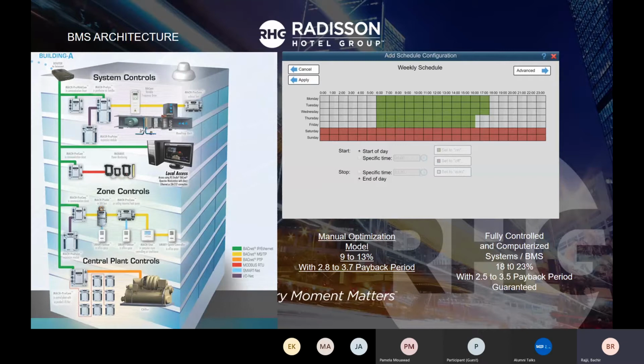But there is always human error, which means an automated system is more accurate with much less error. From studies and experience, a manual optimization model following a checklist would save between 9 to 13%, guaranteed, with a payback of 2.8 to 3.7 years depending on the hotel, equipment capacity, etc. However, a fully controlled BMS system would guarantee savings between 18 to 23%, with a payback period of around 2.5 to 3.5 years.